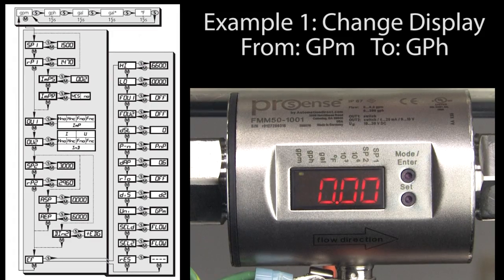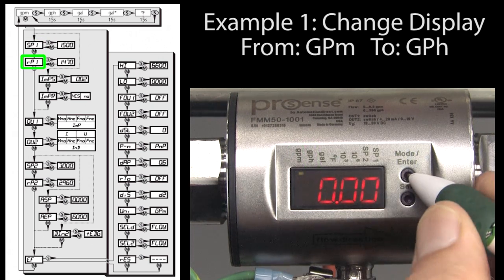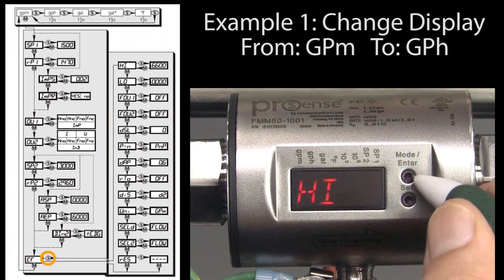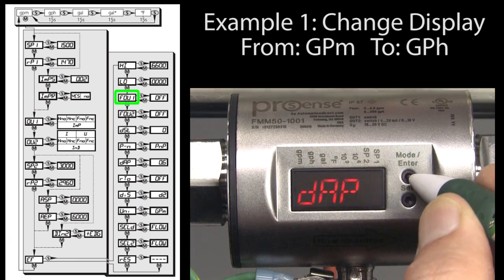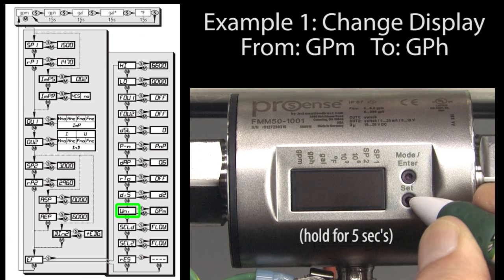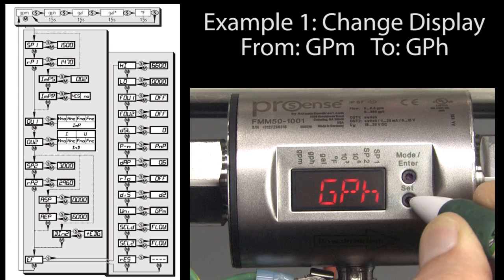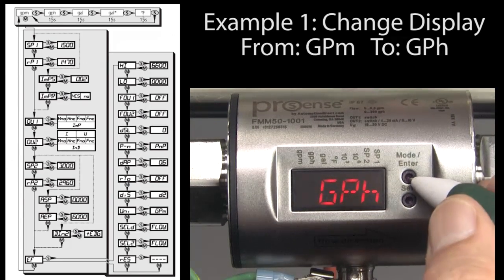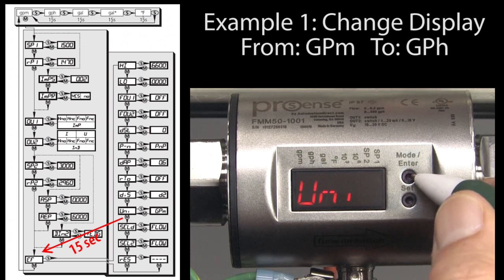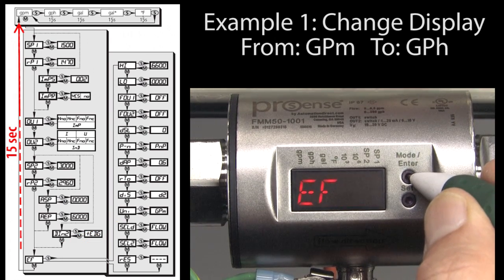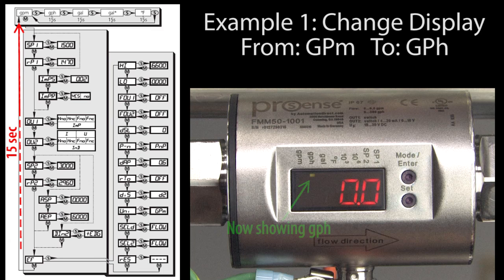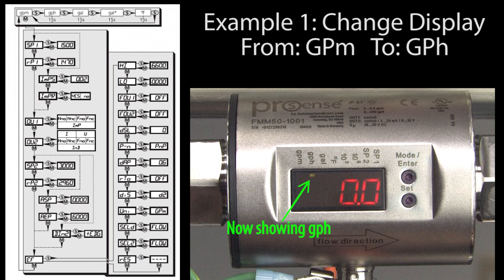Looks like we're currently showing gallons per minute. Let's change that to display gallons per hour. Press the mode button until we get to the extended function menu, select that, then press the mode button to get down to the units parameter. Hold the set button until the display stops blinking. Now we can cycle through the options. We only have two here and we want gallons per hour. To accept the change, press the mode button again. It's quicker to just press the mode button to get us back to the extended function menu and then back to the main display.